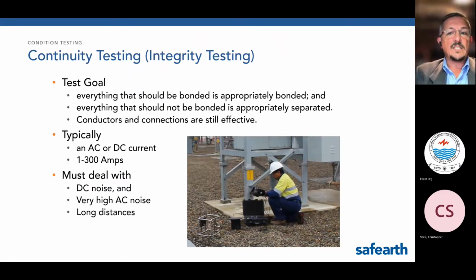Let's dig into condition testing first. In IEEE Guide 81, it's referred to as integrity testing. In some parts of the world, it would be called continuity testing. But the idea is to demonstrate, to validate by measurement that everything that should be bonded together is appropriately bonded together, and that everything that should not be bonded is appropriately separated. You want to be able to achieve that quickly, efficiently, and with accuracy.